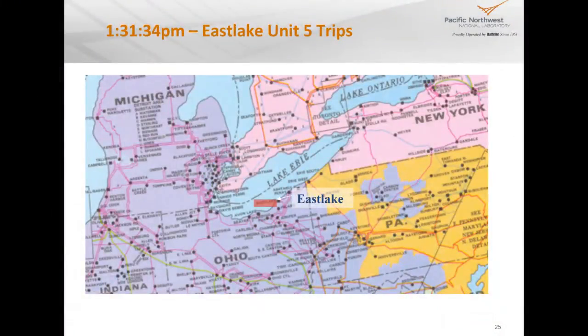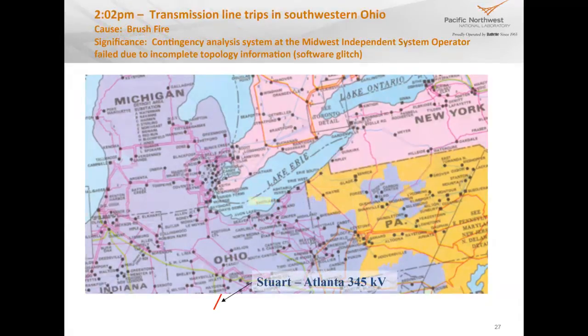Okay, so the first thing of relative interest that happened on that day was a power plant on Lake Erie tripped. The reason it tripped, it was a failure in the exciter system. So the voltages were low, so they're trying to get the voltage increased by putting out more reactive power. And that's managed through the exciter system. And that went offline, and then it tripped the plant. So we lost 600 megawatts, and we lost a critical voltage support there in that area. So that's near Cleveland.